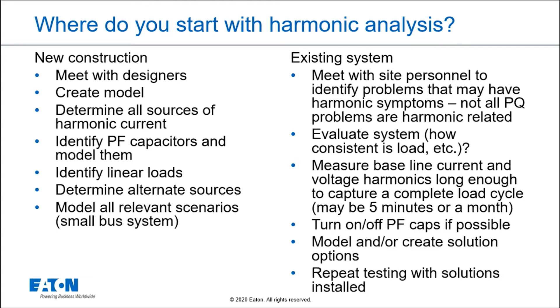If we're going to look at an existing system, there's probably a reason why we're modeling or looking at that system — somebody's determined that there's a harmonic issue. So you want to talk to people from the site, determine what the symptoms are telling you, and remember that not all power quality problems are harmonic problems. There could be transients, voltage variations, SAGs, and stuff like that.